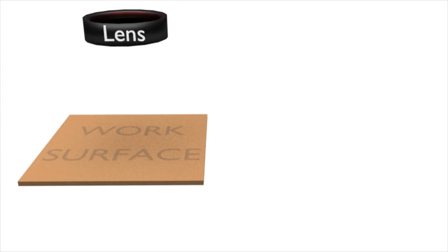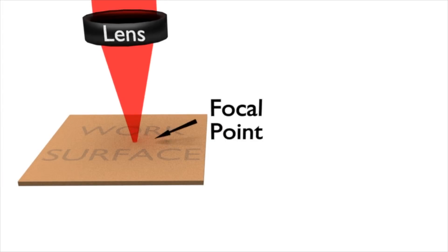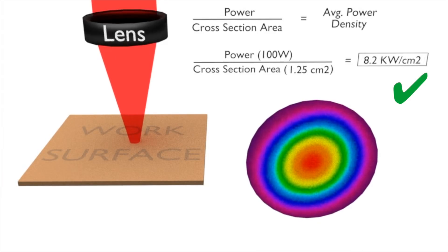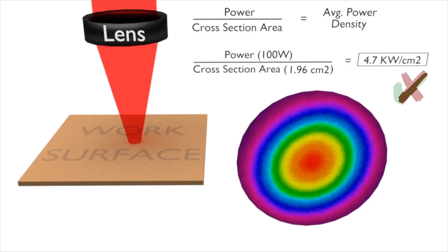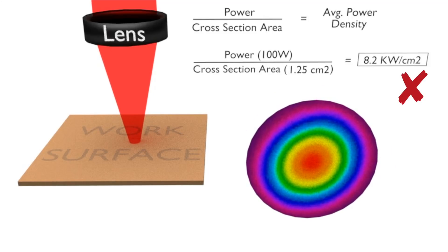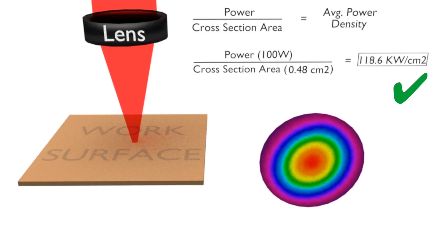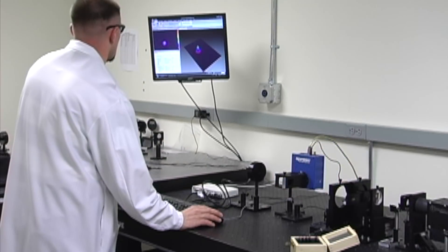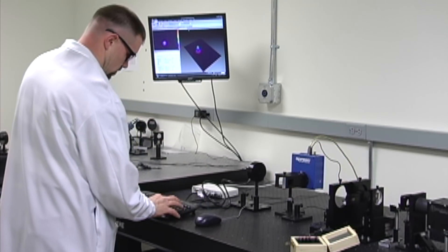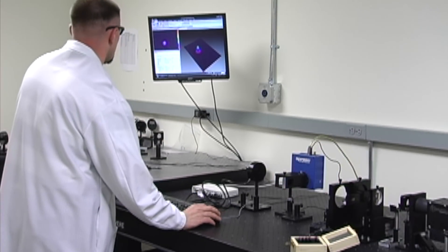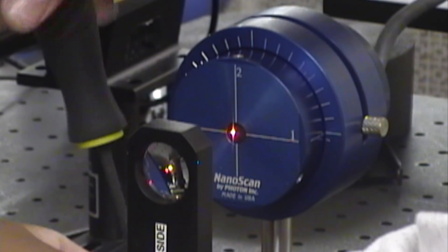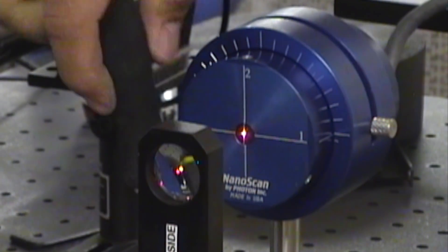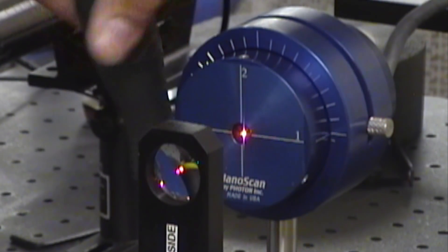Reduction in laser power in conjunction with increases in laser spot size reduces power density. This efficiency loss will eventually cause the system to alter the process. Periodic measurement of the laser system is the best way to manage these changes and to better predict when corrective maintenance needs to be performed.